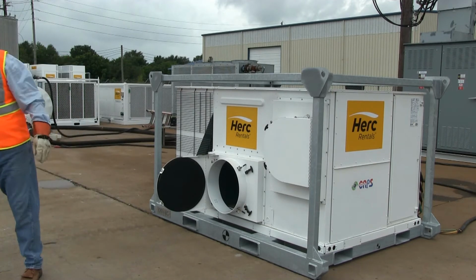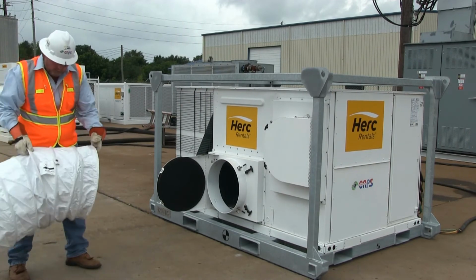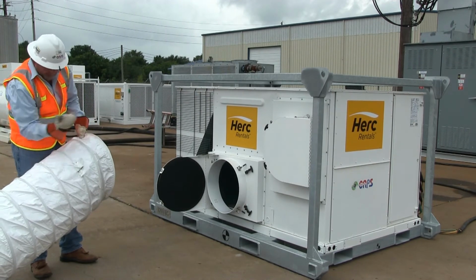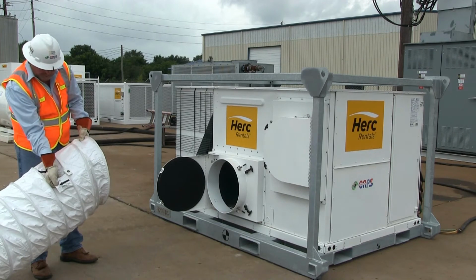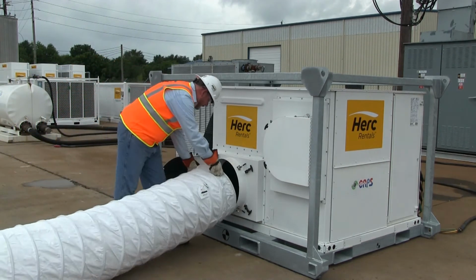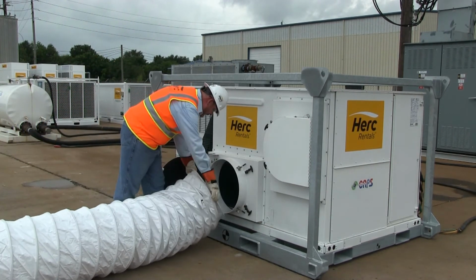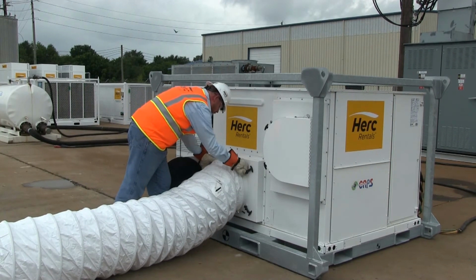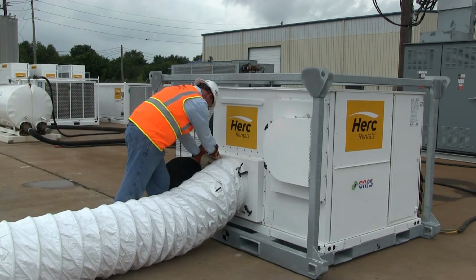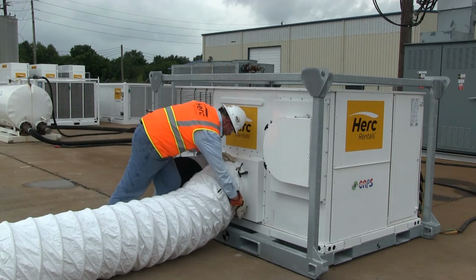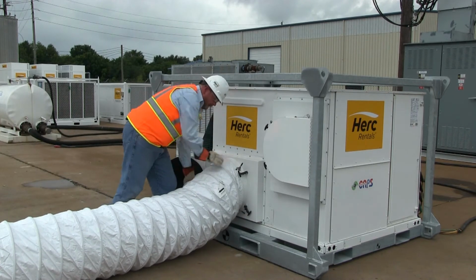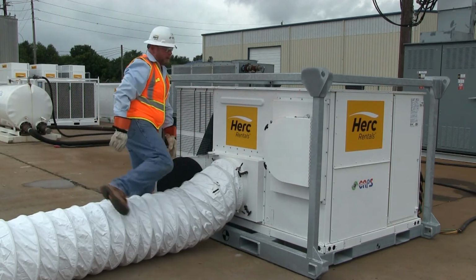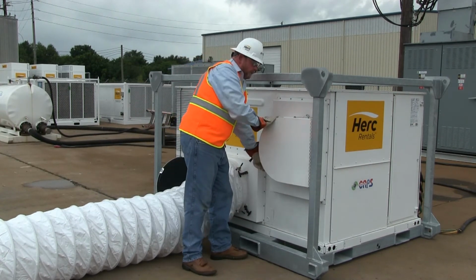You're going to take the return air duct. Please note the direction of airflow. We're coming out of the unit, so you want to make sure it matches the tag. You're simply just going to take the ring, pull the duct in, hook it up on here, drop the friction clamps down on each side, all four of them, here and here. Now that's hooked up, and then we're going to repeat the process for the inlet side.